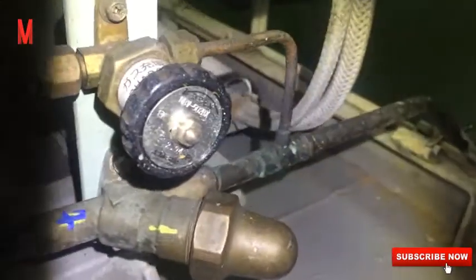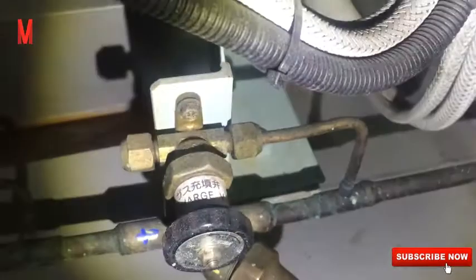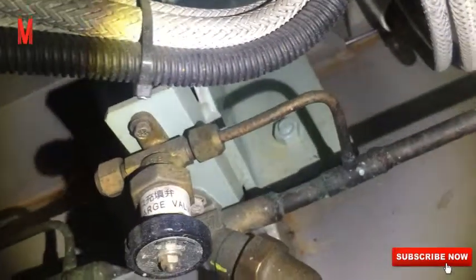And then the condenser, this is a heat exchanger na nagko-convert ng high pressure and high temperature refrigerant from the gaseous state to the liquid state. So from refrigerant gas, gagawin niya itong liquid. In the condenser container, cooling water or the cooling seawater flows around the condenser and absorbs the heat from the refrigerant. So yung nagpapalamig sa condenser is cooling seawater.